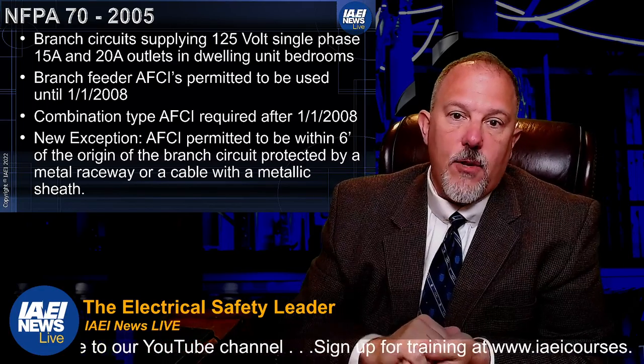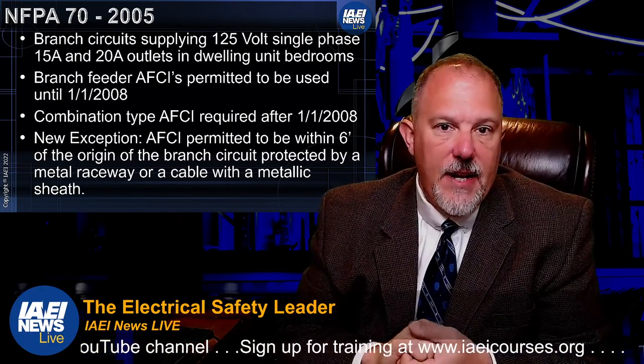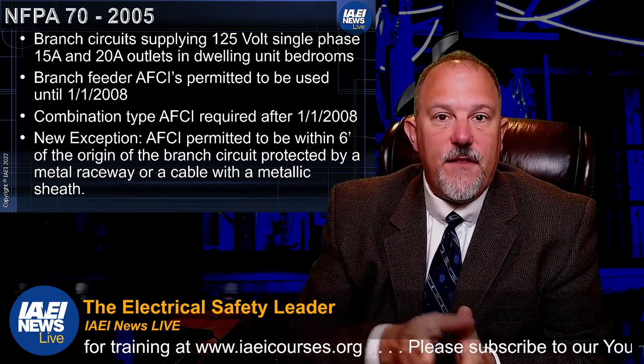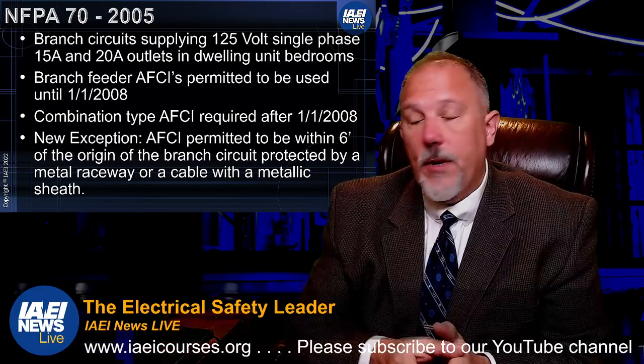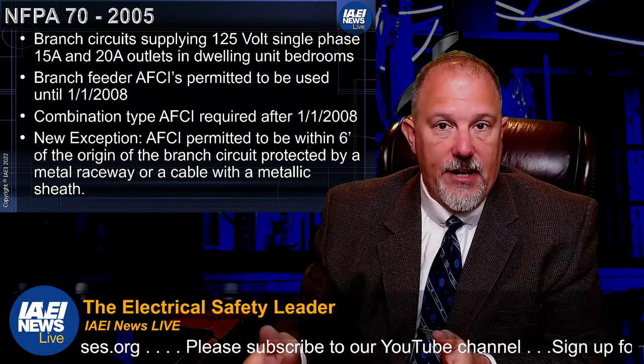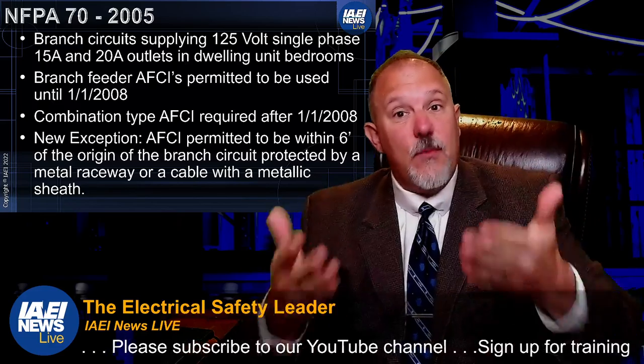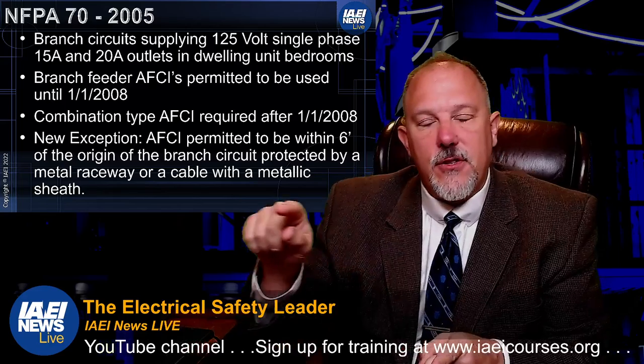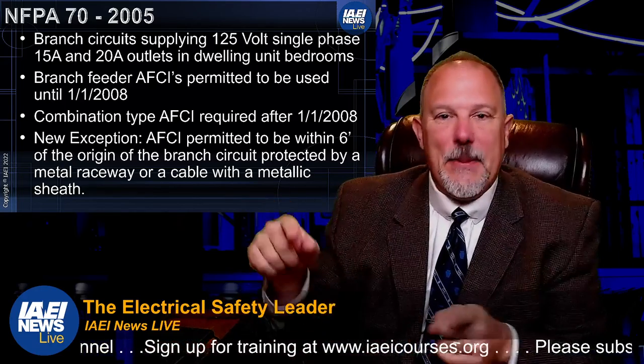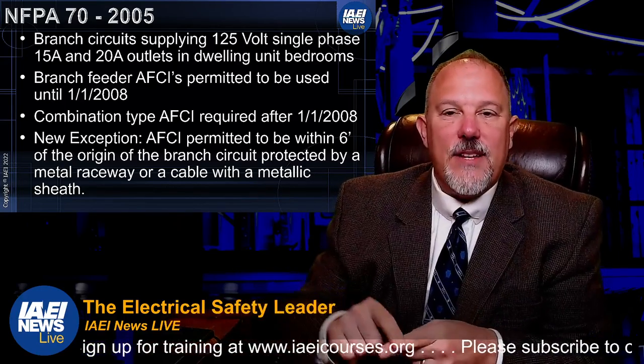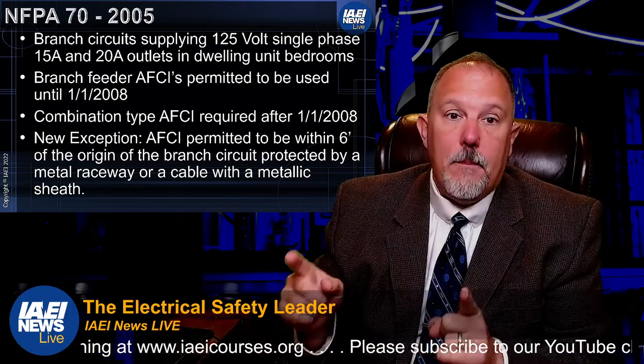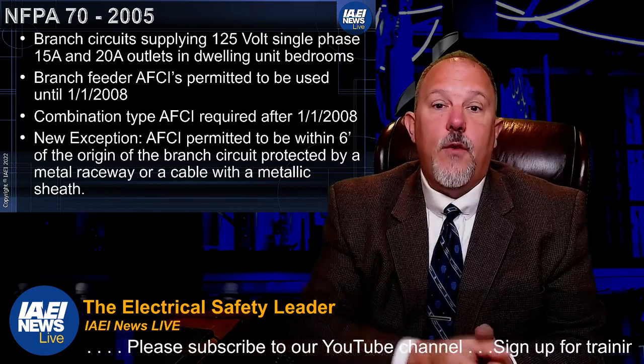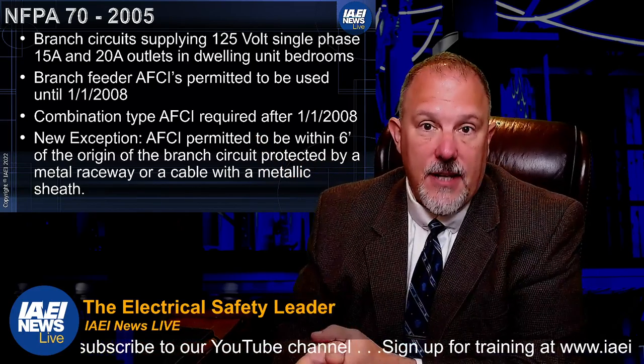In 2005, branch circuits supplying 125-volt, single-phase, 15- and 20-amp outlets in dwelling unit bedrooms remained required. The 2005 code began phasing out the branch feeder type AFCI in favor of the combination type AFCI. This is important to understand because you'll see another reason it matters when we get to the 2014 code.